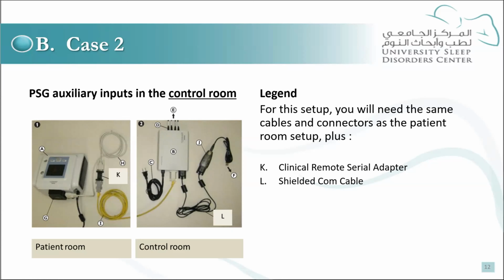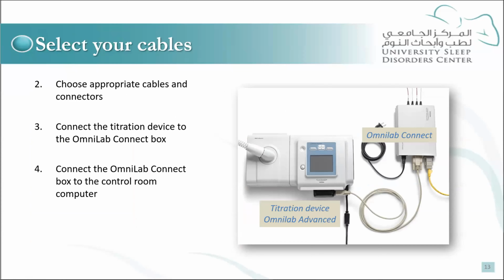Of course, we are not going to detail this. It needs to be worked out with the manufacturer that you have in your unit and with your biomedical team in order to make sure that this setup is working properly. The next step would be to choose the appropriate cables and connectors. You will see that there are many cables and many connector types, so you need to choose the ones that are applicable to your setup. Then you need to connect your titration device, as you can see in the picture, to your connecting box. So you need to find the right cables going from the device that you use for titration to the box that will connect the signals to your PSG system. And of course, the third step would be to connect this box, the OmniLab Connect in this example, to the control room where the computer is positioned.